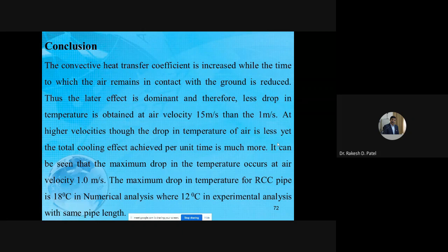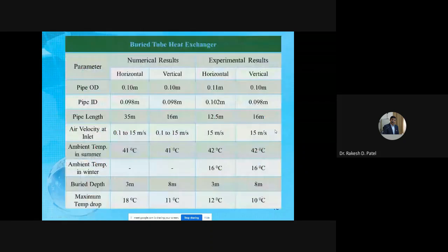So it is easily and well defined in our concluding chart. It can be seen that the maximum temperature drop occurs at velocity of 1 meter per second. Obviously, if air velocity is low, we get the maximum temperature drop. If we go for higher velocity, the minimum temperature drop occurs. The maximum temperature drop for the RCC pipe is 18 degrees centigrade in numerical analysis, whereas 12 degrees centigrade in experimental analysis with the same pipe length. So this is a conclusion table for the earth tube heat exchanger, the numerical result as well as the experimental result.